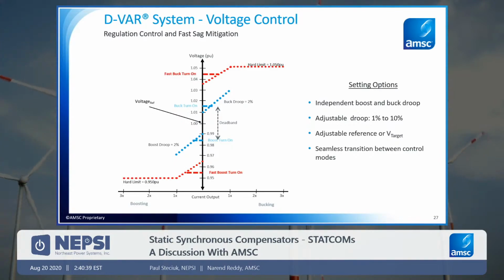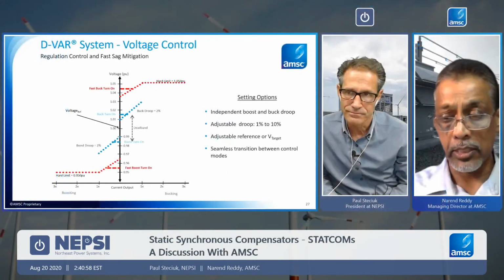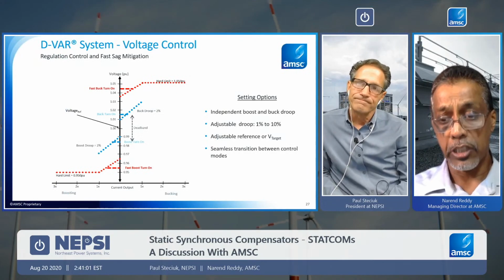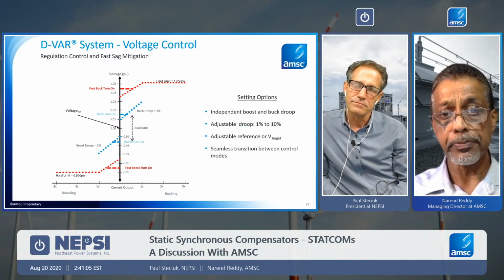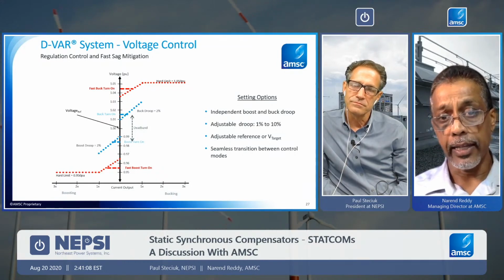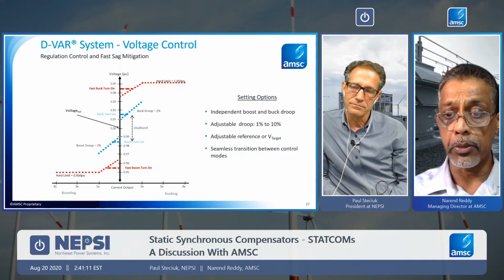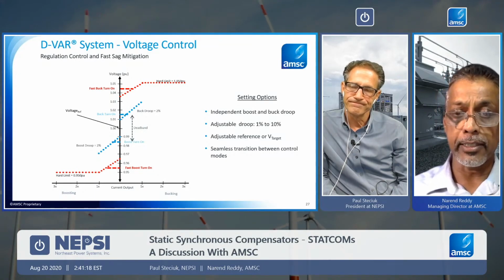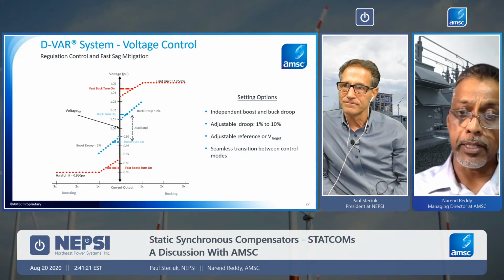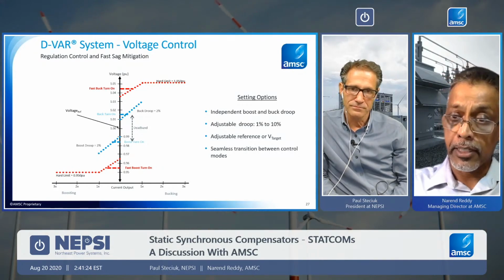While that is operating, the system is also on the lookout for any sags or surges that happen in the grid. If any of those criteria is met for it being a surge event or a sag event, meaning that voltages are below a certain threshold or exceeded a certain threshold, the system transitions over to a different control mode, and the objective is to bring the voltages back into the blue operating range, so that from there onwards, the D-VAR steady state control, or other equipment in the system, might take over the control and manage that as designed.